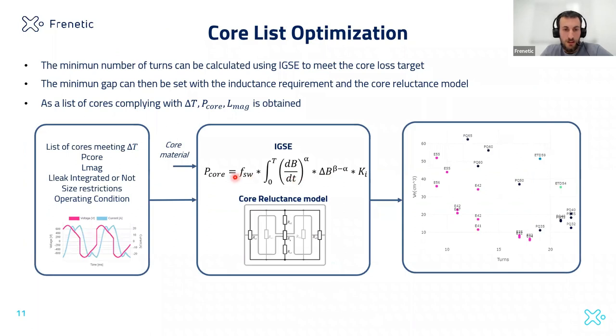The next thing we need to do is, based on this core loss target and having, let's say, the inverse of the Steinmetz equations, the improved generalized Steinmetz equations, we can get how many turns we need in our core. So let's say I want 10 watts, I have this core, doing the reverse math, we can get, okay, I need then 25 turns. So this is the first step, and we should always do this with the proper operating conditions. So this means at the worst case scenario for the transformer, which means at the lowest switching frequency with the highest input voltage.